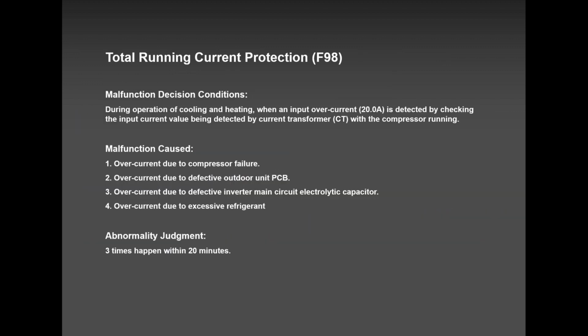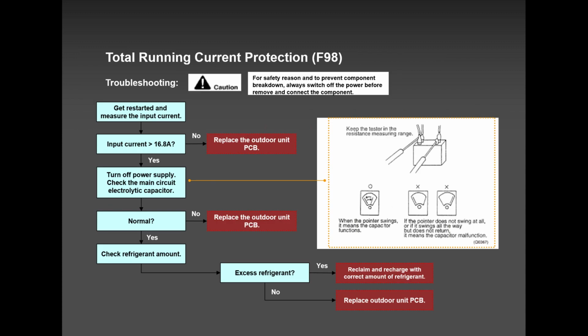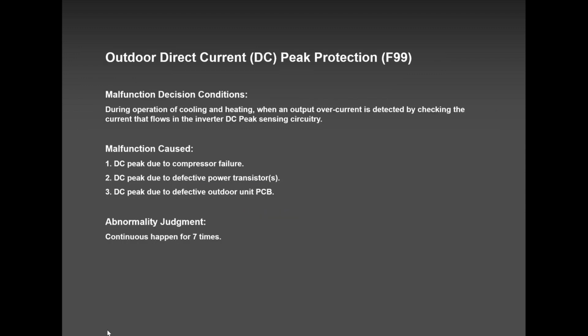F98, same story, compressor failure or outdoor PCB. But before you condemn both of them or either one of them, power reset. Power reset for 10 to 15 minutes and see how it goes. I have never had an F98, guys, but it can happen. I had a few F99s and that was a power reset and it got rectified.